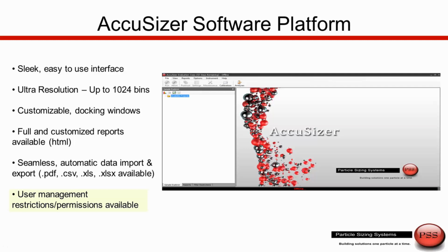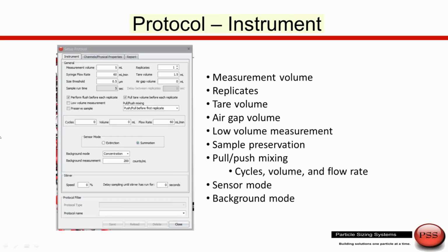The screen we see here is the screen where we could set up a protocol, which is essentially how we program the system to make a given measurement. What's the measurement volume we want to make? What's the flow rate through the sensor? What sizes do we want to work on? Are we going to do multiple measurements? Are we going to do replicates?